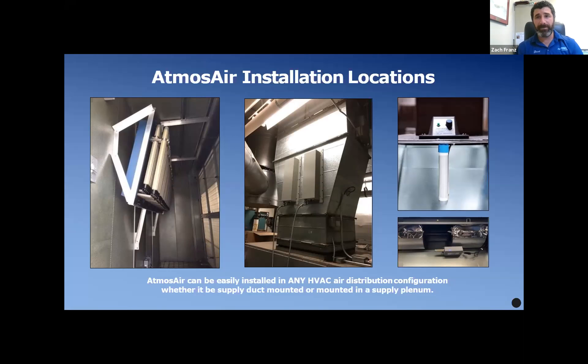What does the technology look like? On the left is our larger system for a larger air handler. This is the supply side of an air system — the supply plenum — where after the fan and the filters, airflow goes into the main supply duct and then out into the occupied space. Our multi-core composite tubes sit in the supply side. As airflow goes over that tube, we're stripping millions of ions and pushing them out into the occupied space in a pulsating positive/negative fashion.